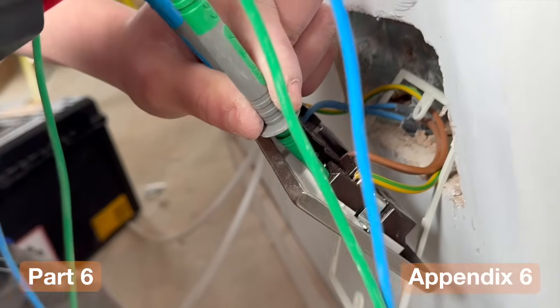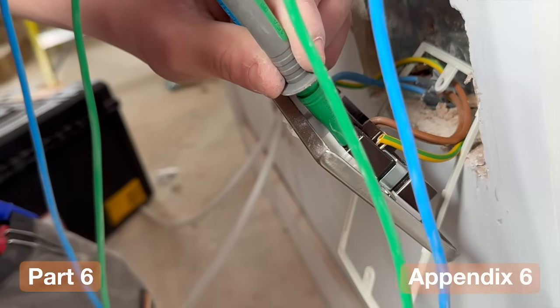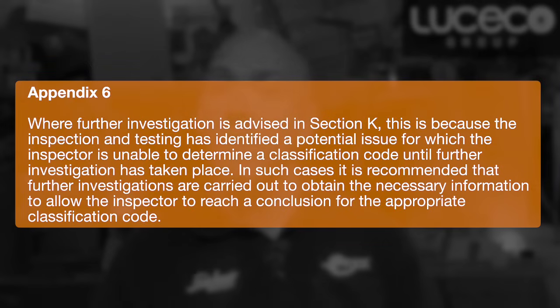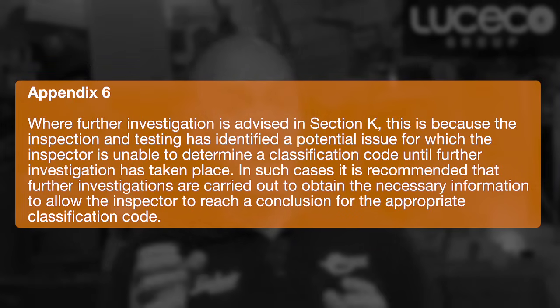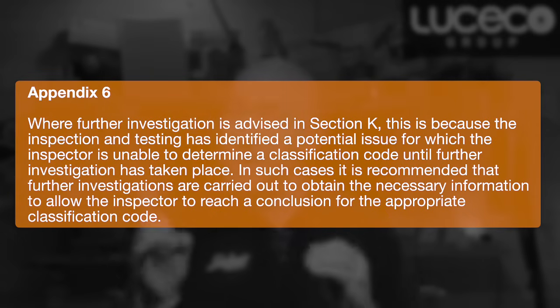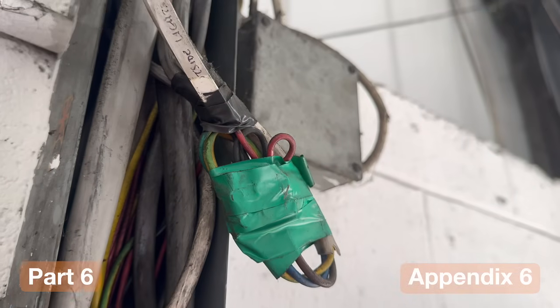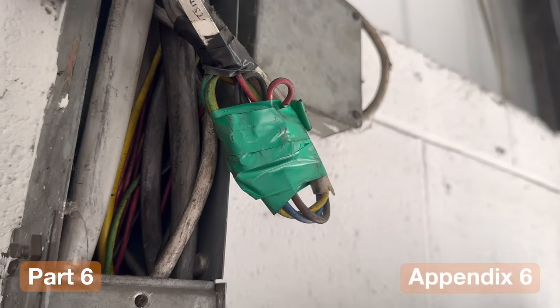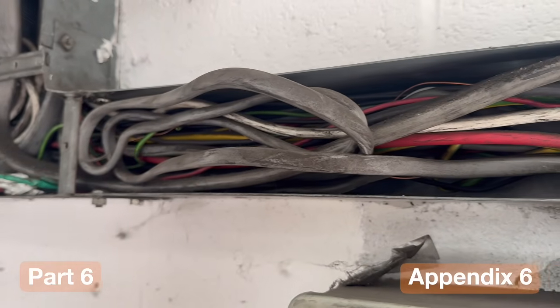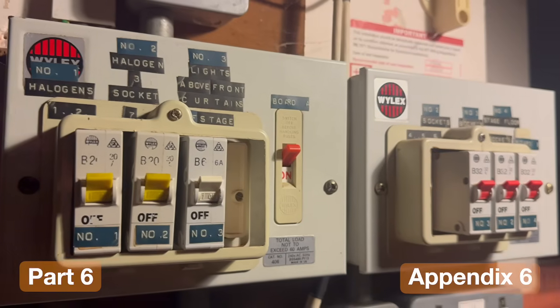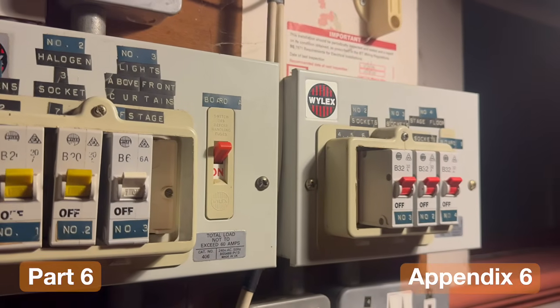Previously, FI was closely tied to an unsatisfactory outcome. It was often treated as a default where something was not quite right, but could not be confirmed at the time of inspection. That has now been clarified. FI is no longer a classification of the condition itself. It is simply a statement that further investigation is advised because a proper judgment cannot yet be made. So if you can determine that something is dangerous, it should be coded C1. If it's potentially dangerous, it should be coded C2. Then we have C3, which is used where improvement is recommended.